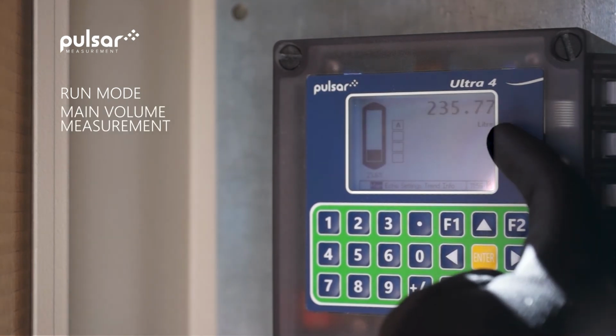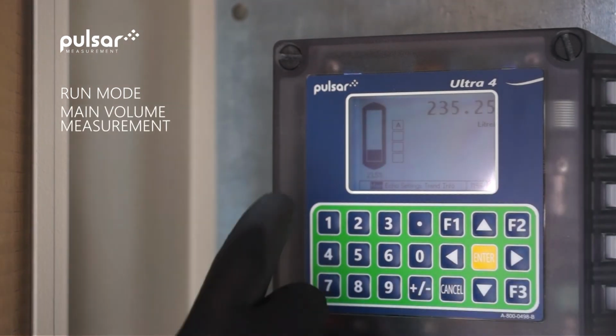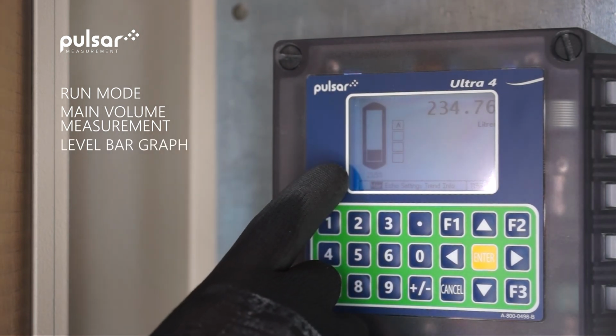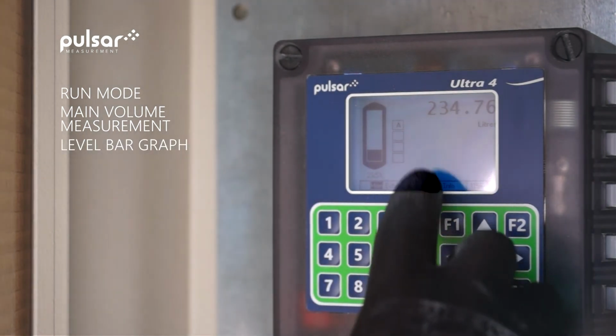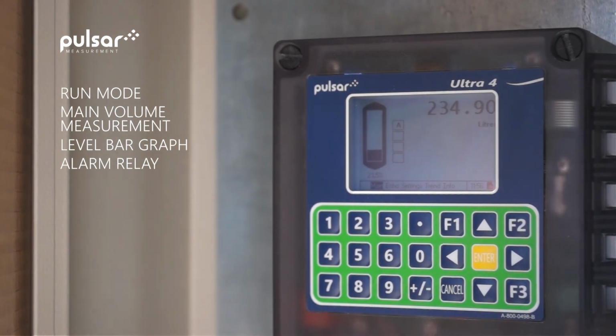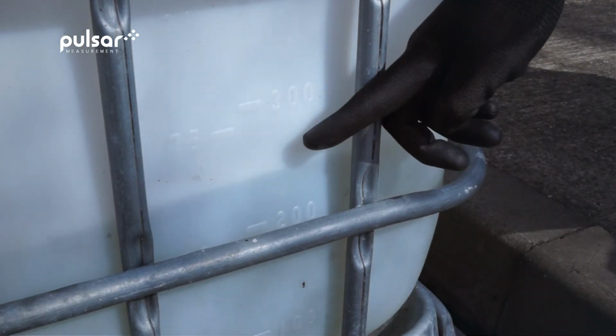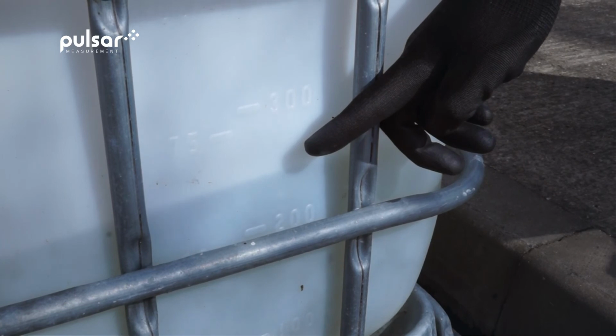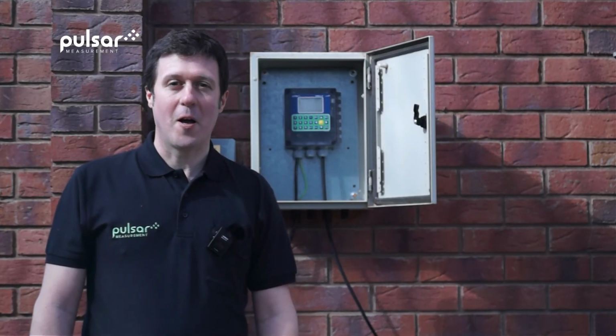We can see our main volume measurement on the screen. We can see the bar graph indicating the level on the left hand side, and we can also see indication of the alarm relay. We can also see the level of water in the IBC against the markings moulded into the container.